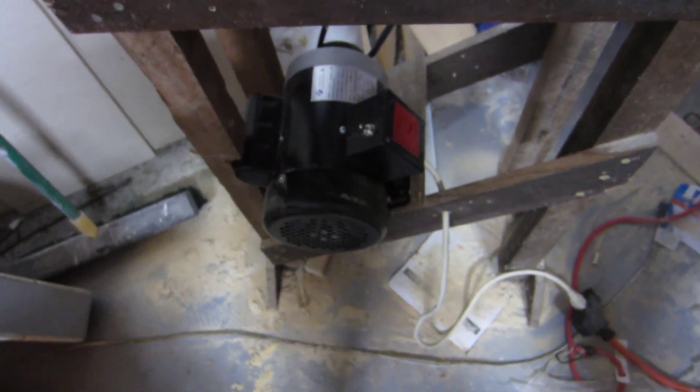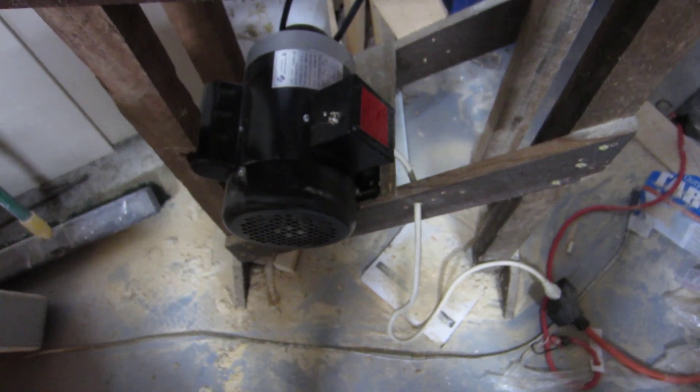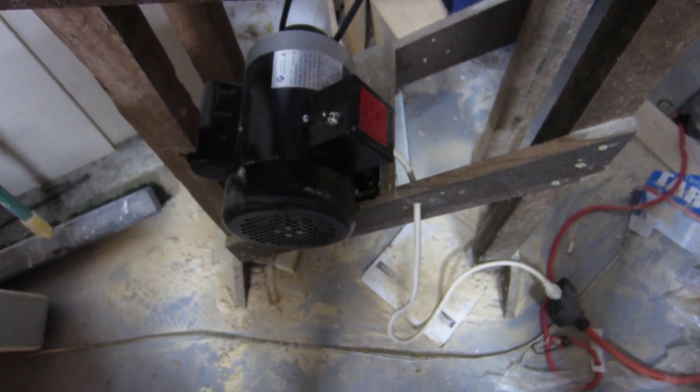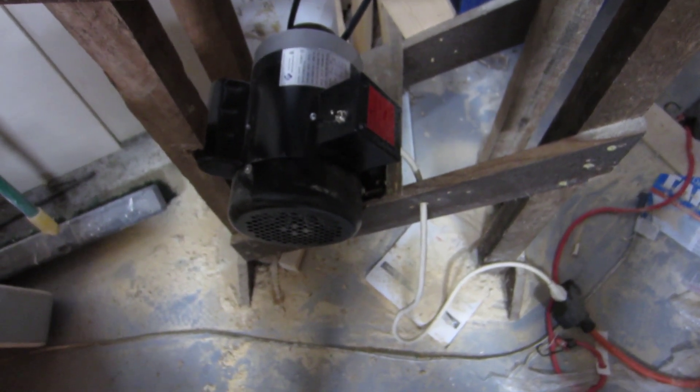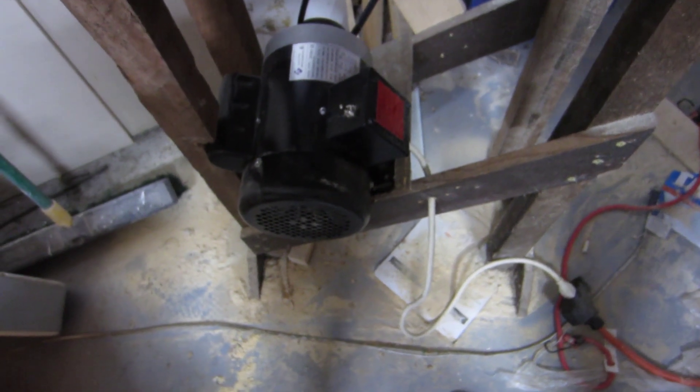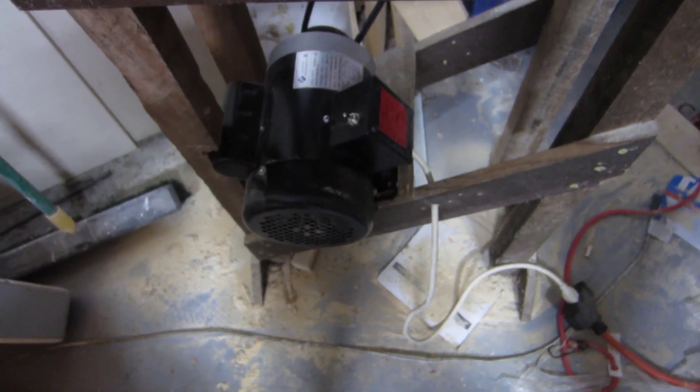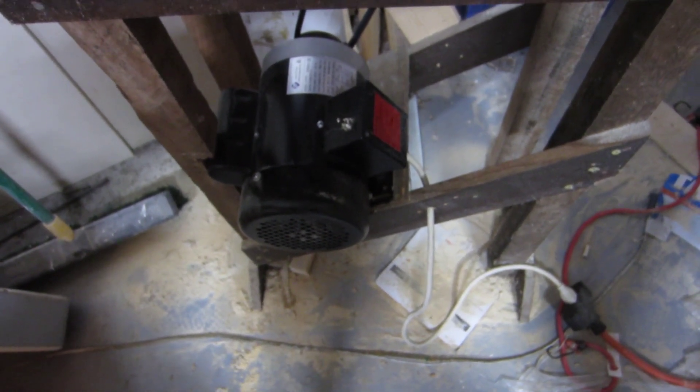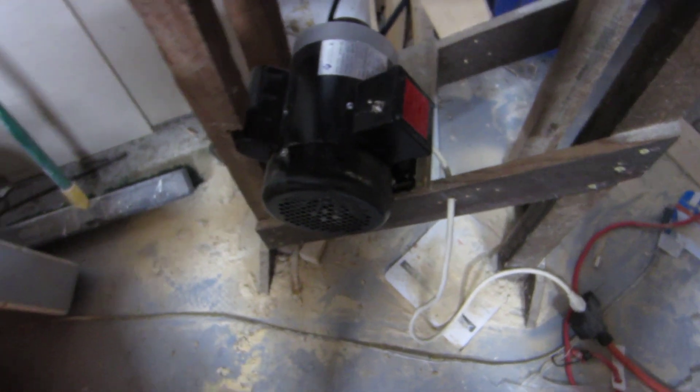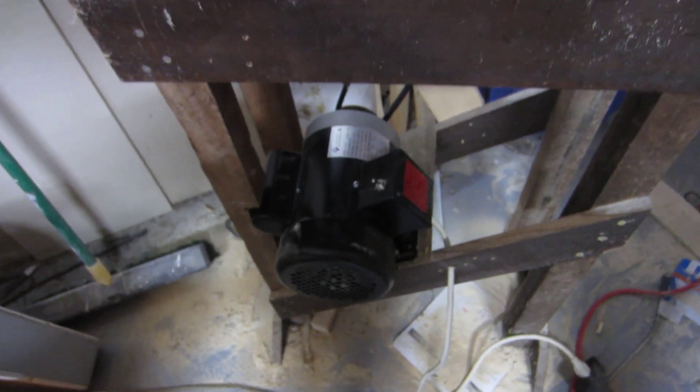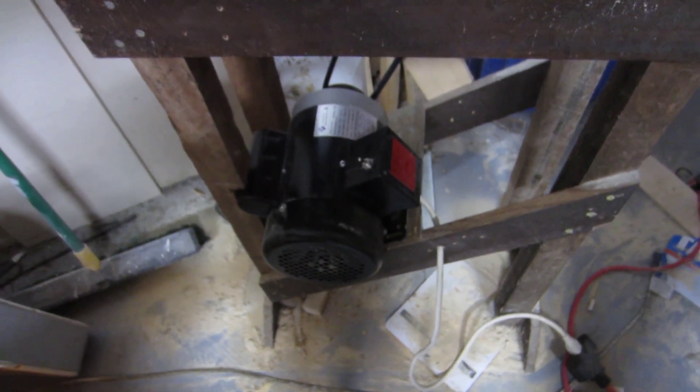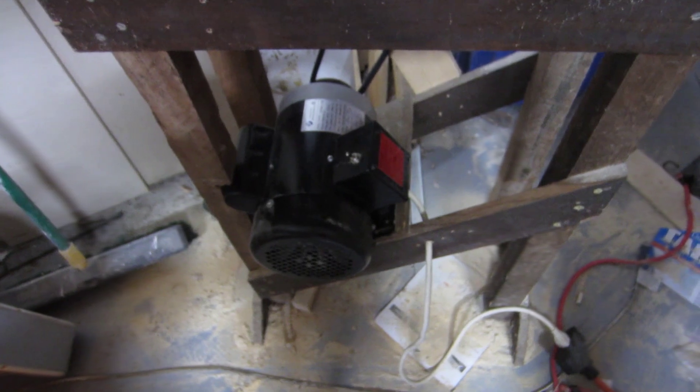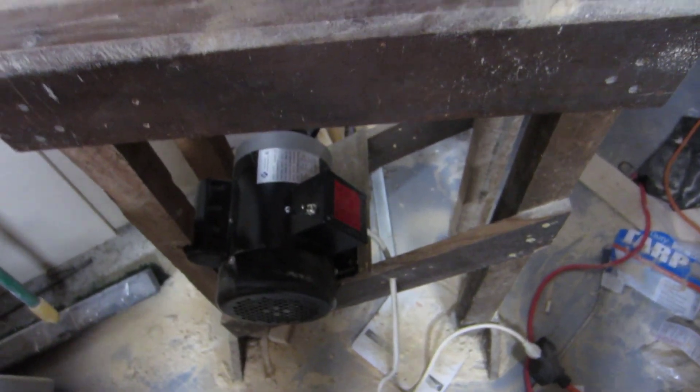I will also note this thing is running extremely cool. The other motor would have long been really really hot by now. I hope that this helps you replace some motors. Obviously I could have undersized this quite a bit. It was 1/6 and now it's 3/4, so it's quite a lot more power, which I think is fine. It's gonna draw more power, but the amount of torque is so much better, along with replacing the belt that was ancient and delaminating. As always, thanks for watching.